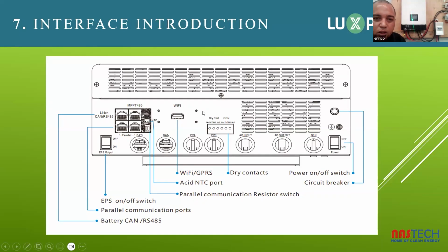When you connect your generator to the machine, the application of the generator is mainly to charge the batteries. So you will use the power from the battery to supply your load. And once your battery reaches a certain SOC, the generator kicks in and puts the energy back into the battery. So the generator does not actually do the load performance. The inverter and the battery take care of the load. But as soon as the battery gets to a certain level on the SOC, the generator supplies power back to the battery, like a solar panel would when you're using a solar panel on this inverter.